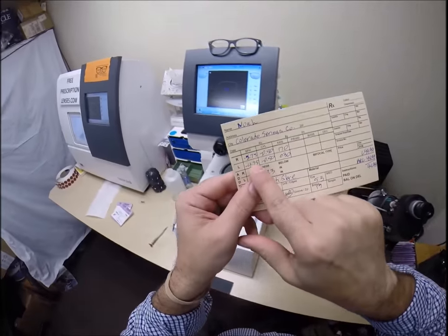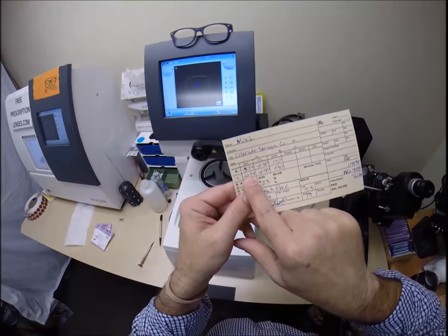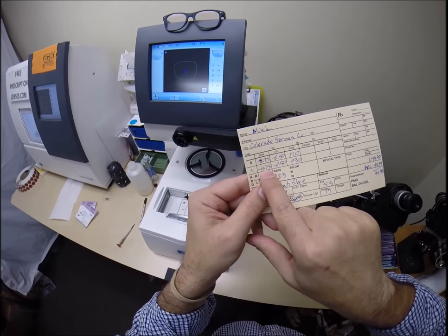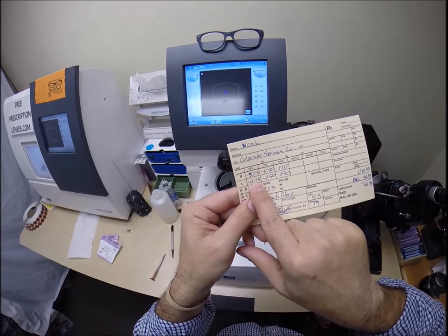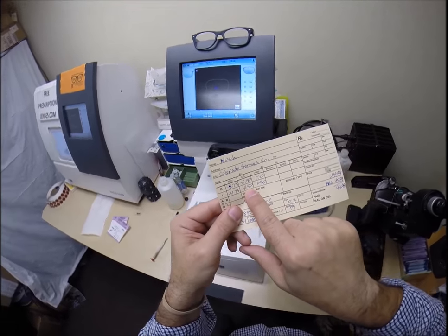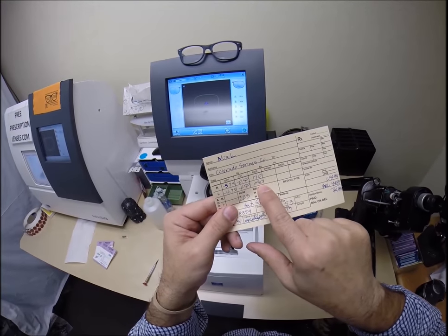Now, your left eye needs a whole diopter less correction. So, let's see, 16, 19. You need 19 steps of nearsighted correction in your left eye. Still an additional two steps of astigmatism correction in the left eye. But we're going to turn that fine-tune knob to 30.